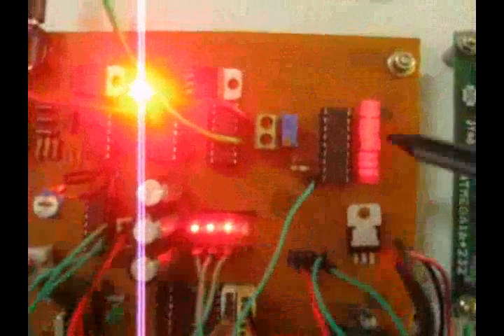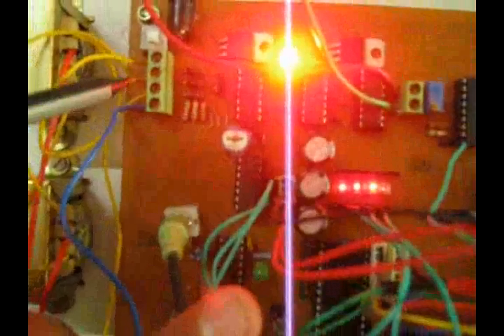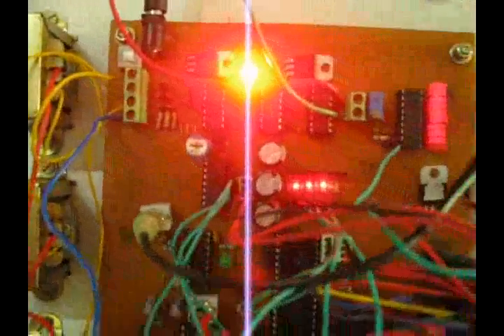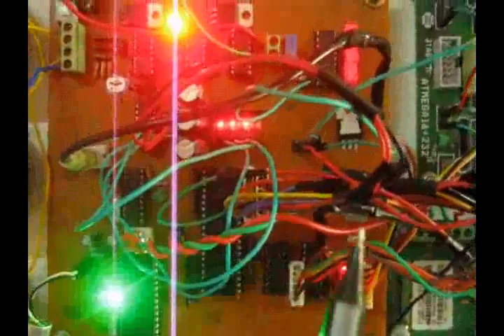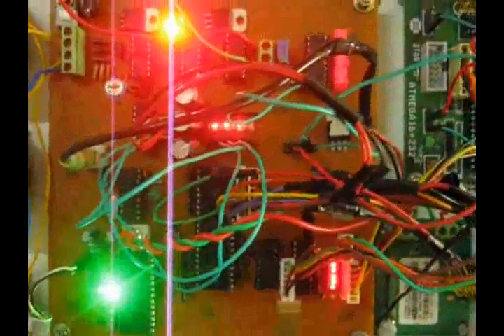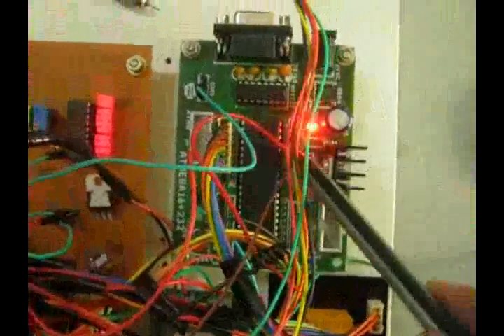Here you can see the 10 LEDs are glowing, which means all the phases are in correct phase and available. And here is a phase loss detection circuit. Here we can see three LEDs glowing, 1, 2, 3, that is R, Y and B. This means all the three phases input here are available for the motor to operate. There are two modes. One is the manual mode of operation and here is the automatic mode of operation.